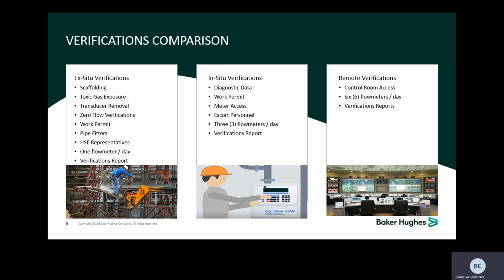The benefit here is we take the transducers out, and since a lot of these flares are dirty processes, we're able to clean them and put them onto a zero flow box where we perform the verification. From there, if testing is done and our technicians determine it's passing grade, we provide a verification report. That report is given to the environmentalists, who give it to the regulators, and sometimes audits happen after that.